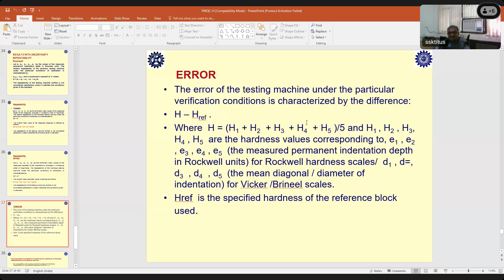So the input quantities considered for evaluating the uncertainty of hardness measurement by the testing machine I have already mentioned. Here it is written: the repeatability of the testing machine by taking 5 readings, that is the measurement of the reference hardness block coming from the hardness machine. The resolution of the indicator of the hardness machine, since the hardness machine will have a certain resolution, that component will come. And the relative repeatability of the reference block used for the hardness measurement. So 5 measurements you are making, so that you can get the standard uncertainty from that. There is a standard way, you are all familiar with that. In fact, the standard uncertainty multiplied by the Student's factor and everything you can take, and you will include that as a component in your uncertainty calculation.